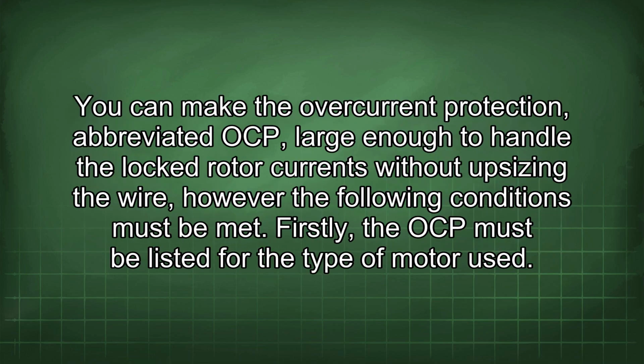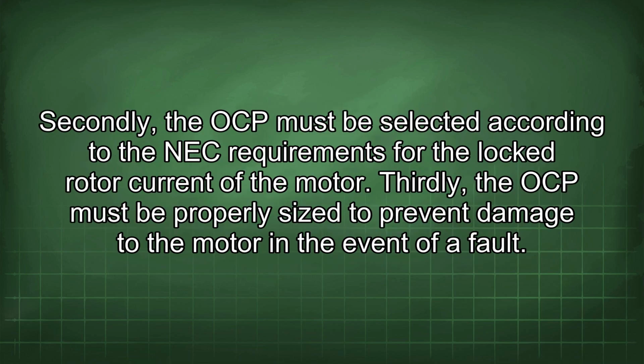You can make the overcurrent protection, abbreviated OCP, large enough to handle the locked rotor currents without upsizing the wire. However, the following conditions must be met. Firstly, the OCP must be listed for the type of motor used. Secondly, the OCP must be selected according to the NEC requirements for the locked rotor current of the motor. Thirdly, the OCP must be properly sized to prevent damage to the motor in the event of a fault.